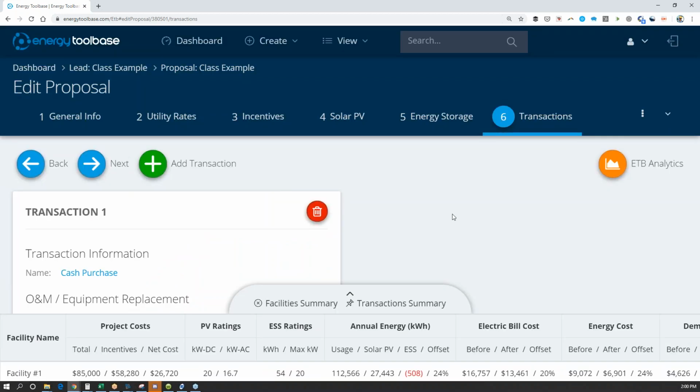And so that's the kind of question. The guidance is if you're going after electric load profiles that are 1 hour or less than 1 hour, which might be a 15-minute power down process, it might be a cloud shutting down a solar array and coming back on again, or it might be an industrial process that uses a tremendous amount of power for a short period of time, going with lithium ion battery or lithium NMC batteries makes sense, even when the demand charges aren't sky high, simply based off you trying to target a very peculiar spiky load.